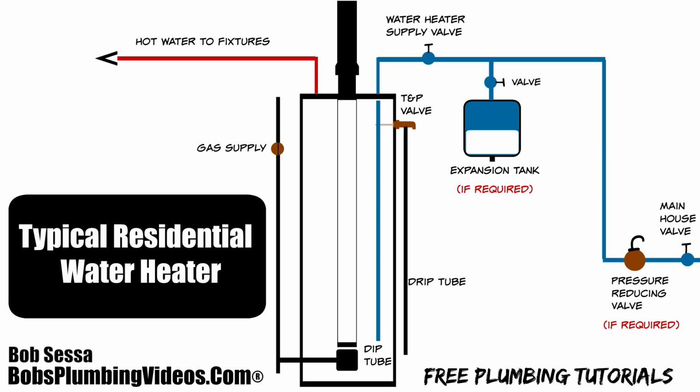And with the expansion tank on there, as the water expands, it'll push up against that air pocket. And then as the water cools down, it'll relax, and you'll have this back and forth motion. So as the water heats, it's kind of like a balloon. It'll expand, it'll contract, it'll expand, it'll contract, and that will take up the expansion.